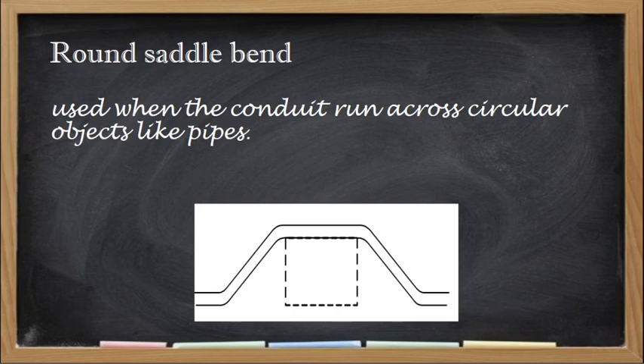The other name for the round saddle bend is the three-point saddle bend, because you will need to have three different bends. If it is rectangular, it is called a four-point saddle bend. Like this photo of a four-point saddle bend, you need four different bends in order for our conduit to traverse this rectangular obstacle.